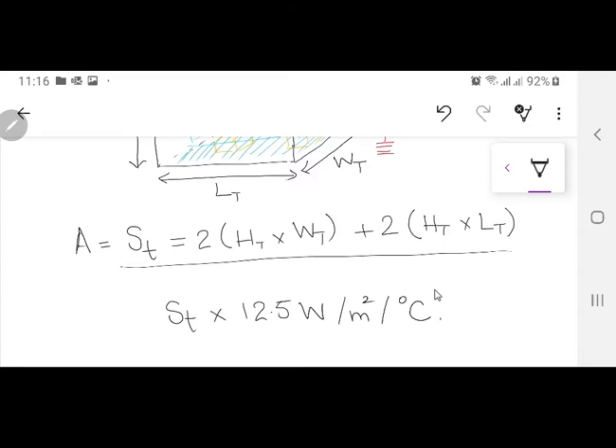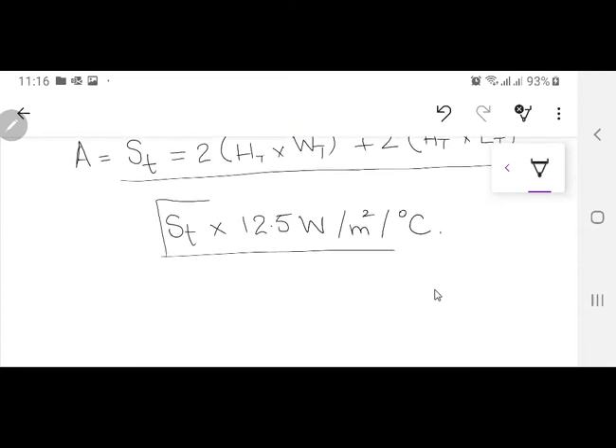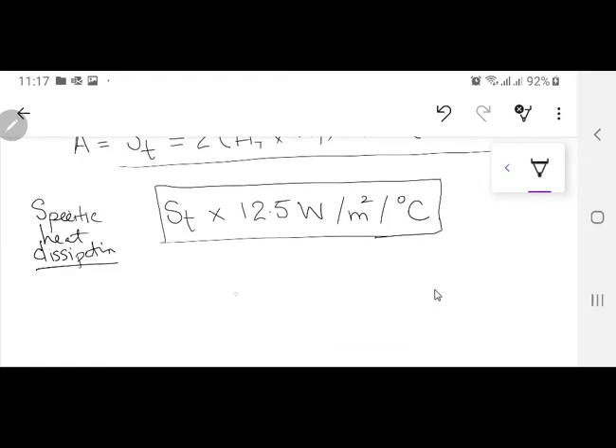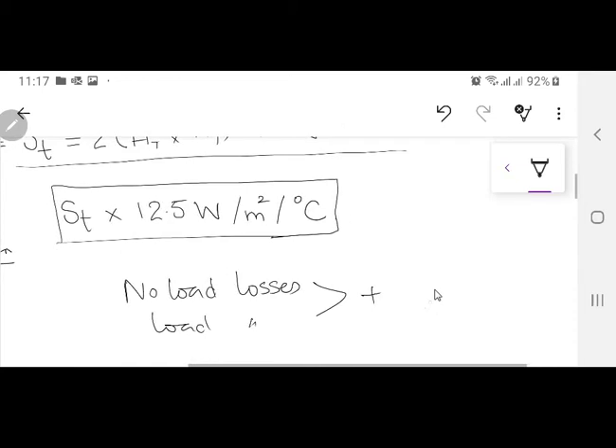Now your design value, or what the designer or consumer required, is 40 degree centigrade rise. So first, this is the total dissipation, or specific heat dissipation. I will first find out the no load losses and the load losses, sum them together, and that value is the total losses I want to dissipate. That losses divided by this factor will tell me the temperature of my transformer tank.